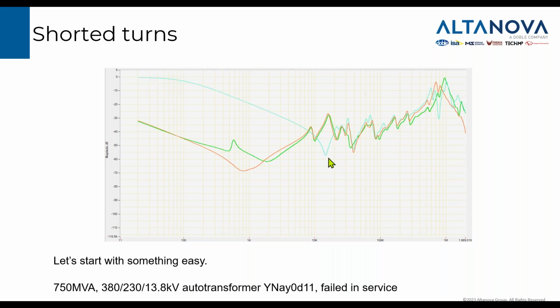So the conclusion was easy. There were short circuits inside the winding, even though there was none outside the transformer; it was inside the winding. The transformer was damaged. We knew that from other sources as well, from DGA, from the history of the events, so it was obvious.